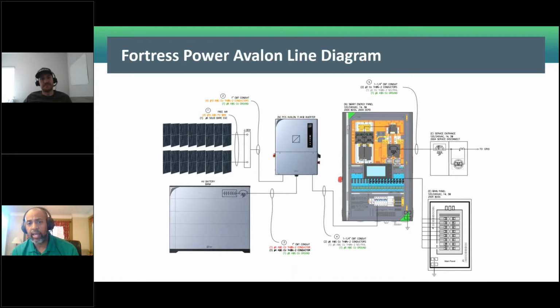The relay capacity in this Avalon Smart Energy Panel gives you the option to control up to 12 single pole circuits and 6 double pole circuits. The relays are 50 amps for each 2-pole, so that's 12 single pole or 6 double pole circuits.